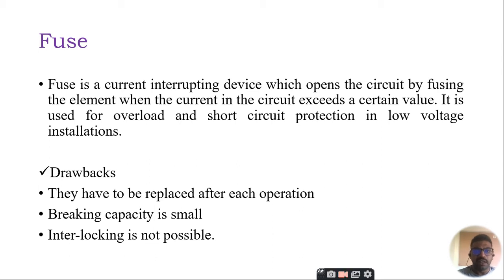Fuse is a current interrupting device which opens the circuit by fusing the element when the current in the circuit exceeds a certain value. It is used for overload and short circuit protection in low voltage installations, usually in three-phase 440V and single-phase 230V.